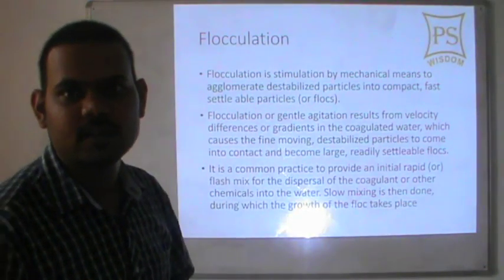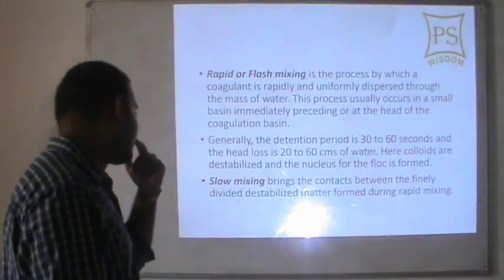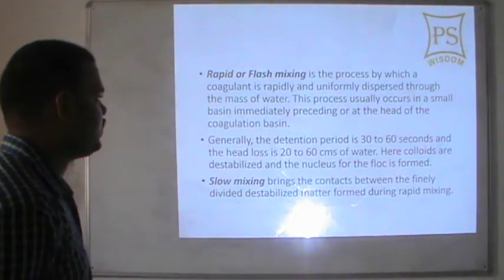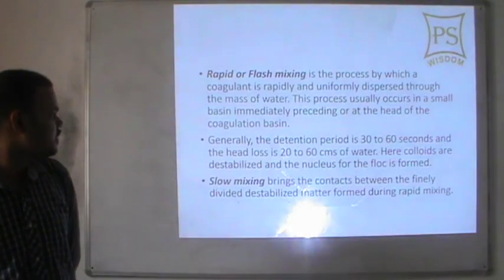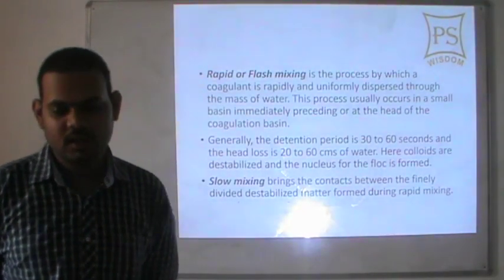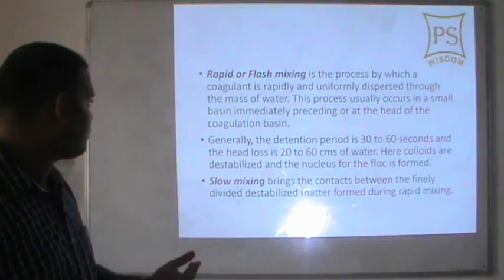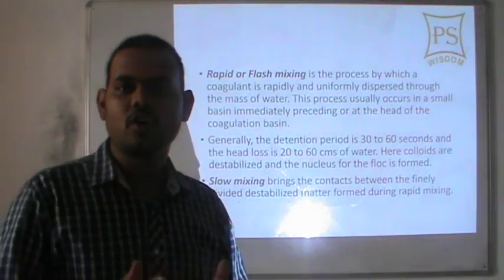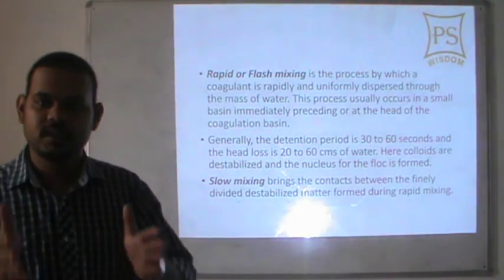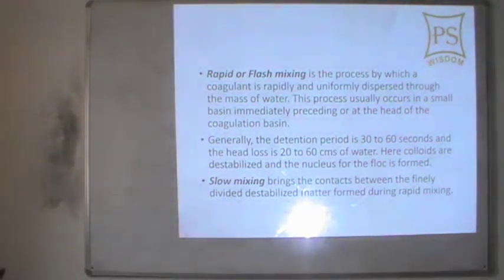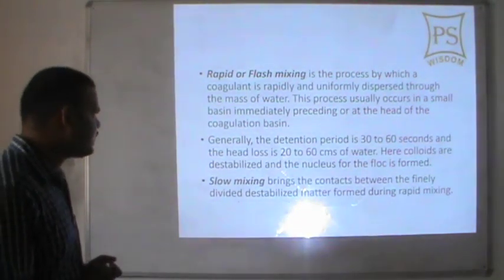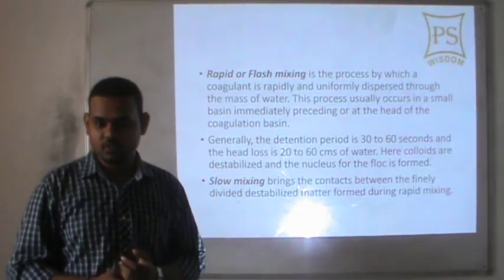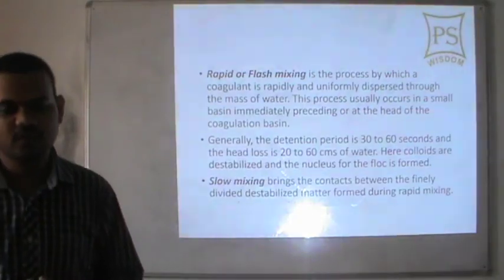Rapid or flash mixing is the process by which coagulant is rapidly and uniformly dispersed through the mass of water. This process usually occurs in a small basin immediately preceding or at the head of the coagulation basin — when water enters the coagulation basin, it is mixed at the entrance. Generally the retention period is 30 to 60 seconds and the head loss is 20 to 60 cm of water.